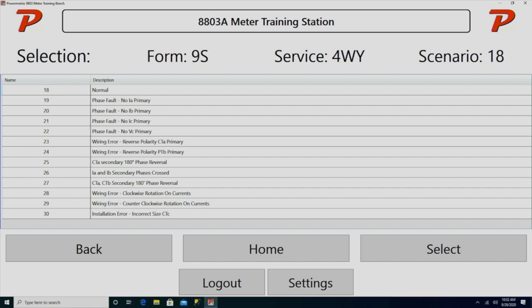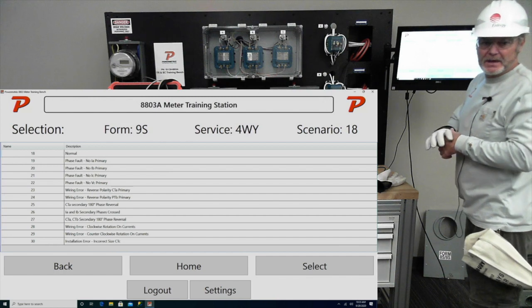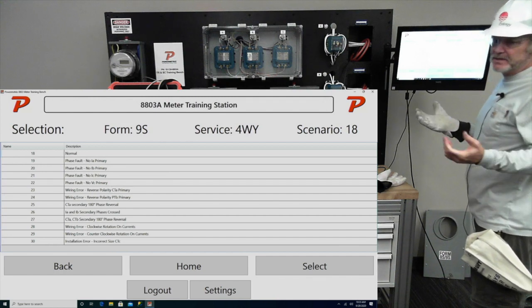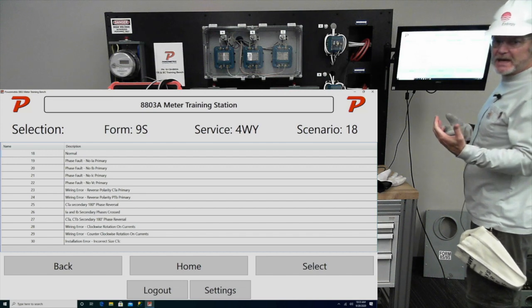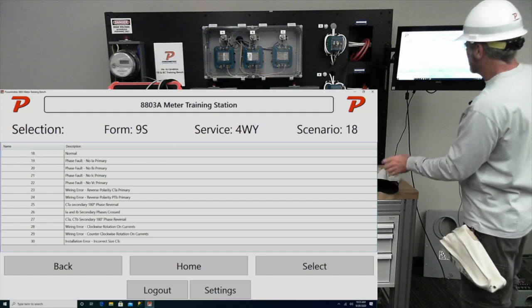Okay, so you got the normal error scenario. I've got phase faults where I have no primary current on A, B, or C phases. I've got phase faults, no voltage on C phase. I've got wiring errors, reverse polarity on primary, reverse polarity on the secondary side. I've got clockwise rotation problems if they've rotated their wiring off as far as their phasing, both counterclockwise or clockwise directions, and then the sweep when they've got incorrect size CTs on there, which is pretty cool. So they can simulate if you had two 200s and a 400-5, and one of them was the wrong size. So all of that's in there, so I can pick any of those. I'm going to go ahead and pick 23 right here.